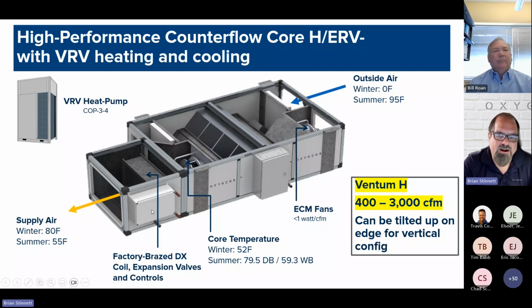I can make that supply air temp as high as 110 degrees, and I can make it as cold as 48 degrees in cooling. So I can do a lot of different things with this. I can add hot gas reheat to it if I want, if I shift to a heat recovery outdoor unit. So just a lot of different options when doing energy recovery and adding VRV heating and cooling.